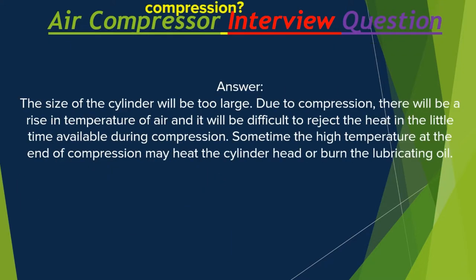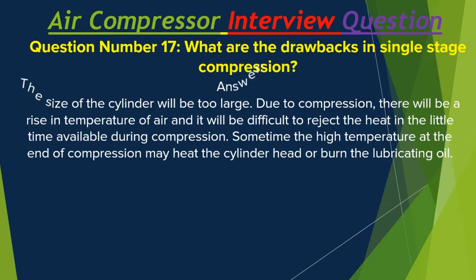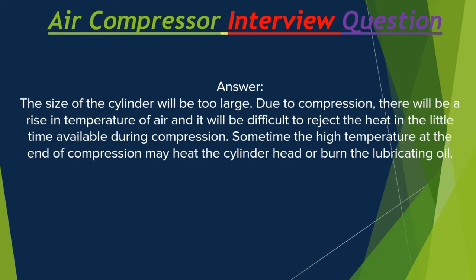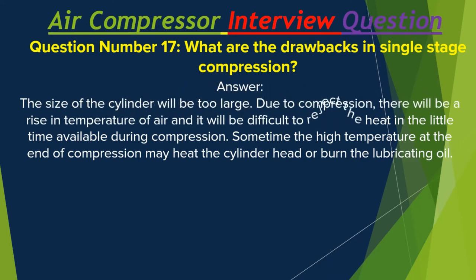Question number 17: What are the drawbacks of single-stage compression? The size of the cylinder will be too large. Due to compression, there will be a rise in temperature of air and it will be difficult to reject the heat in the little time available during compression. Sometimes the high temperature at the end of compression may heat the cylinder head or burn the lubricating oil.